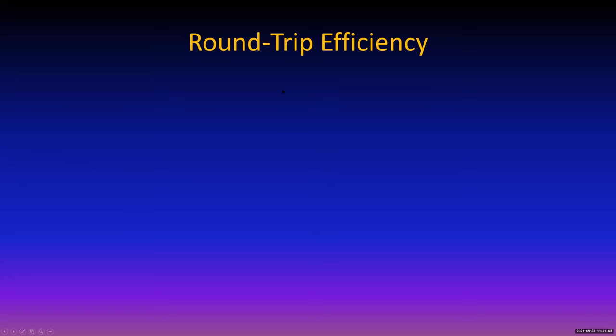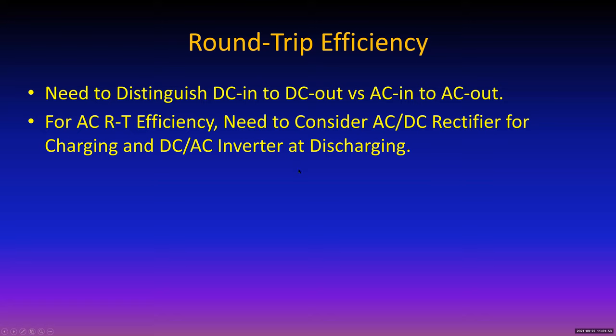Okay, round trip efficiency. In order to compare apples to apples, lead acid to lithium, we need to talk about power in versus power out, or energy in versus energy out. Since most systems now are AC systems, even though the batteries themselves are DC, usually you have AC coming in, going into a rectifier circuit that converts the AC to DC to charge the batteries. Then the batteries discharge out through an inverter that converts their DC to AC. There are inefficiencies in both of these processes, but generally not more than the overall round trip efficiency.